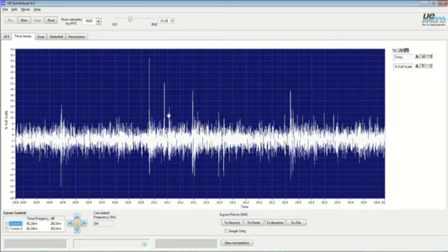And when you see these differences in spacing, that tells you that the timing of the discharges is not linear across the sine wave. Within that 16 milliseconds, there's no predictable pattern on when those discharges are going to occur. That's a key signature of tracking.